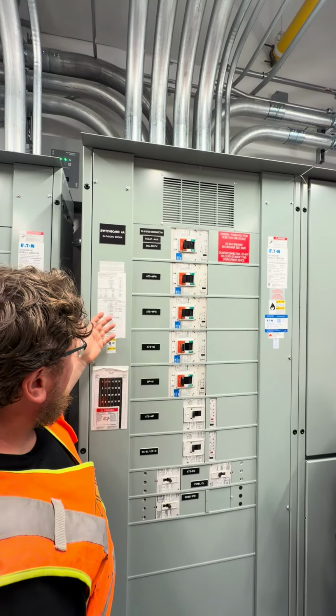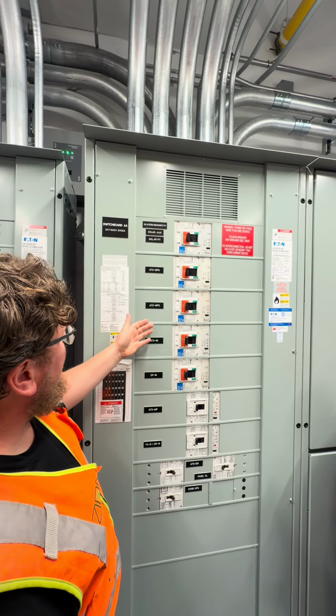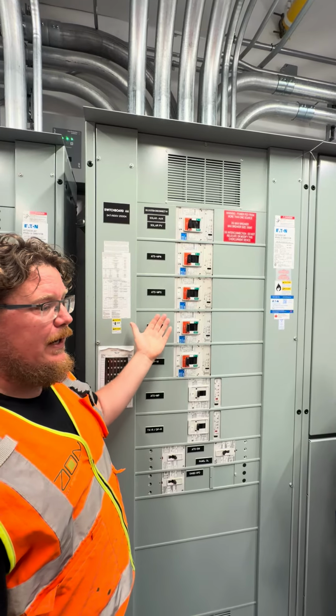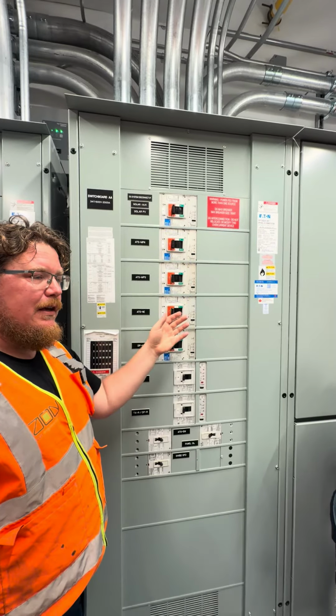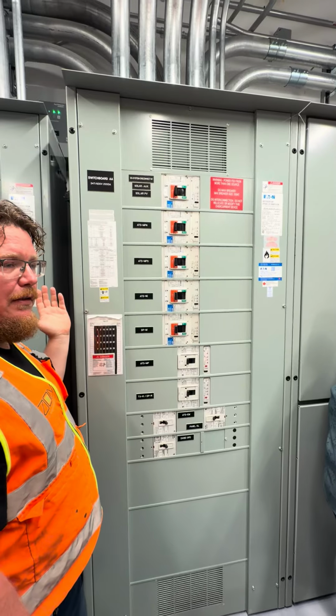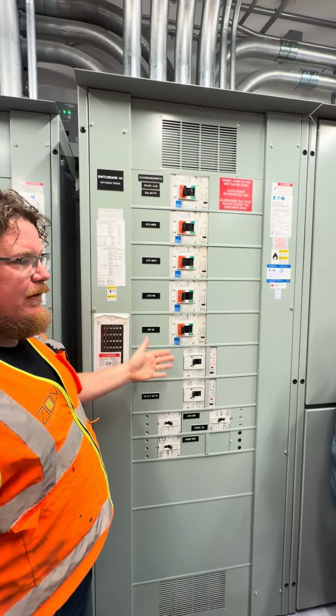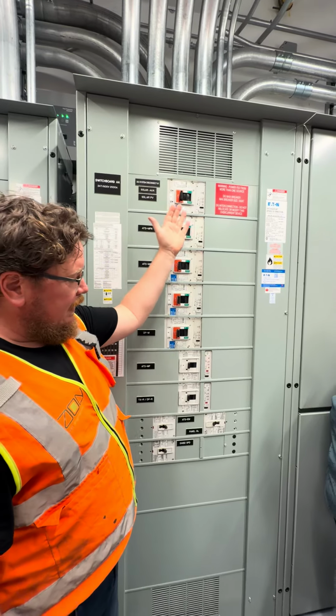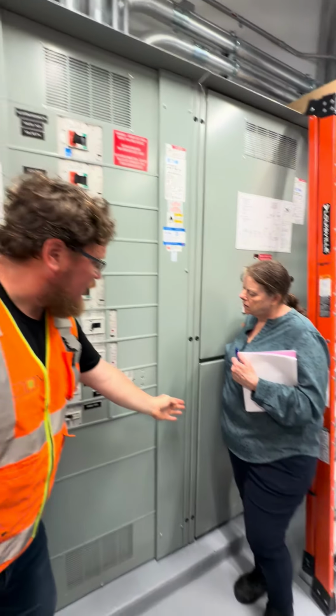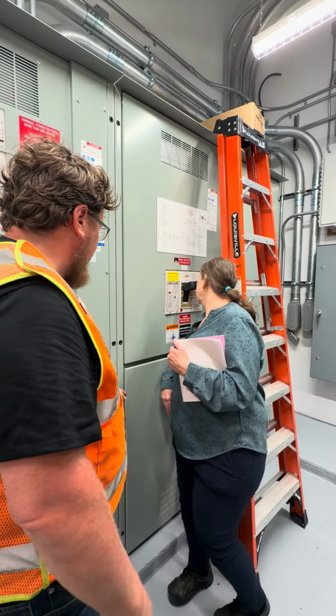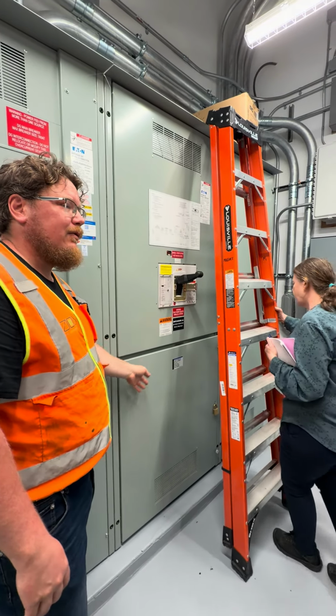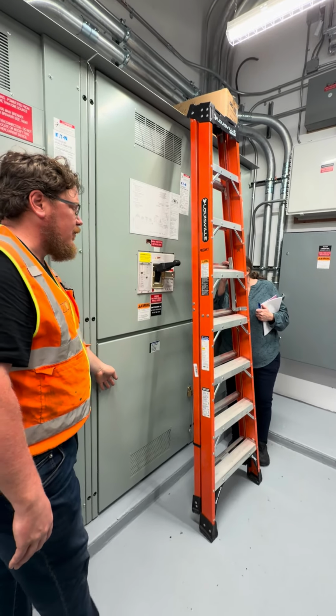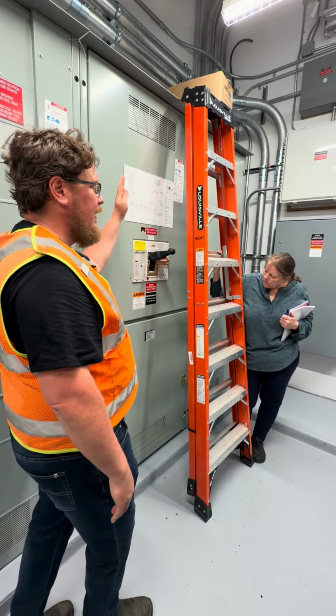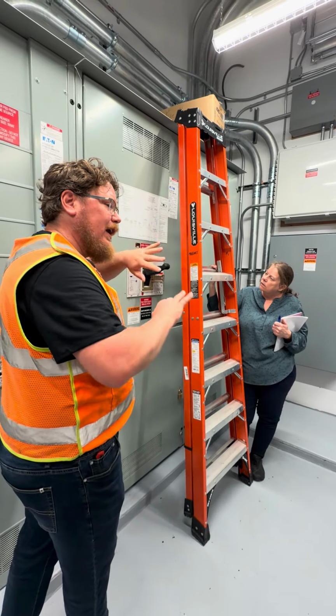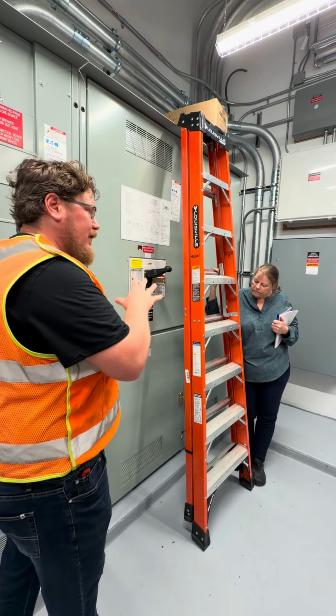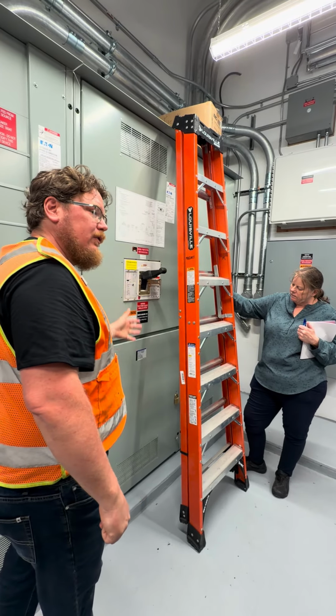So if, say, the northeast wing is pulling extra power, that power will come down, and because it's the path of least resistance, it'll supply those loads. Now if these loads are all satisfied, it will keep sending that power down, back over through the switchgear, and up through the metering section, and that's where the net metering starts happening. So you start getting electrons pushing back up and out to the grid. You don't have to control it — it does it all based on whether there's load or not.